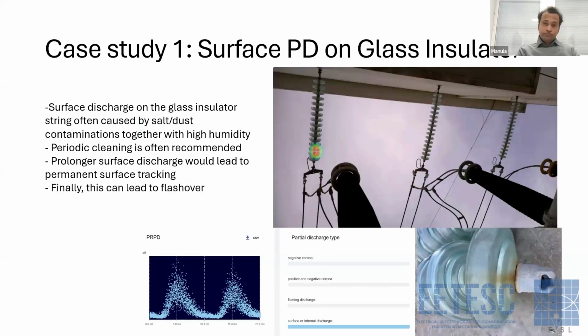Okay, so let's go to practical examples. Here we have this glass insulator string in a high voltage switchgear, and we have detected a partial discharge at the high voltage end of this string. The camera analytics shows this PRPD pattern, and it directly gives it as a surface partial discharge. You can see there are clusters both in the positive half cycle as well as in the negative half cycle. This kind of glass insulator would develop surface discharge because of contamination, as I said earlier, maybe due to dust, salt, together with moisture.